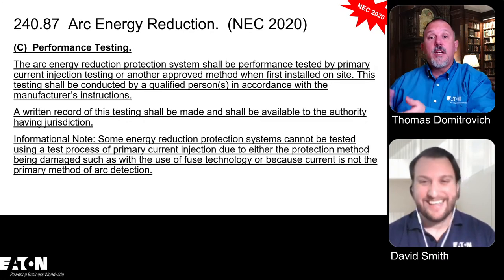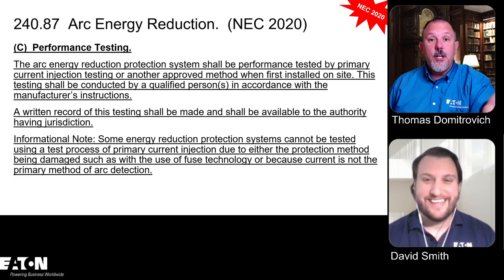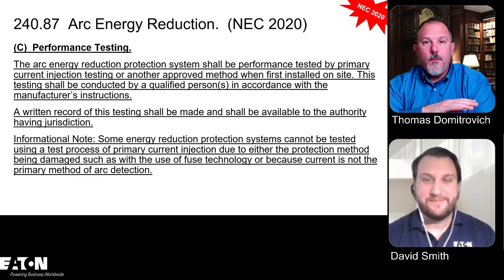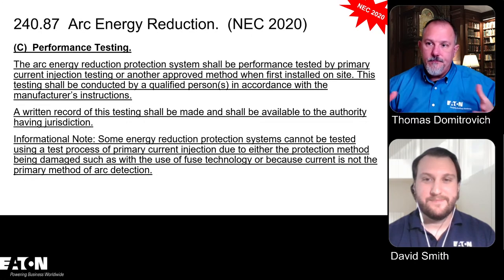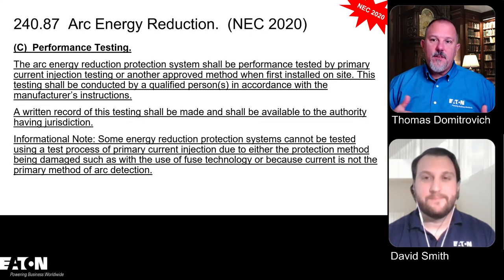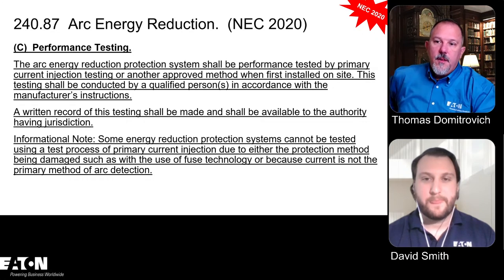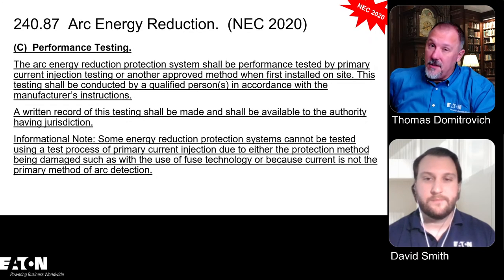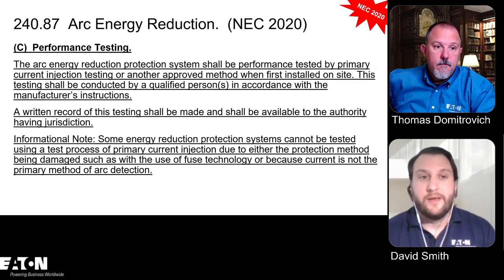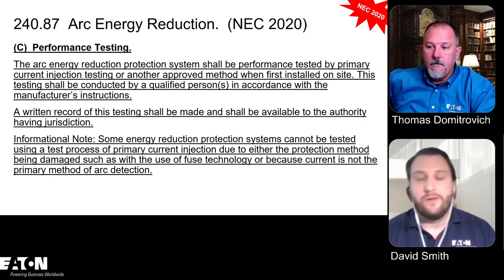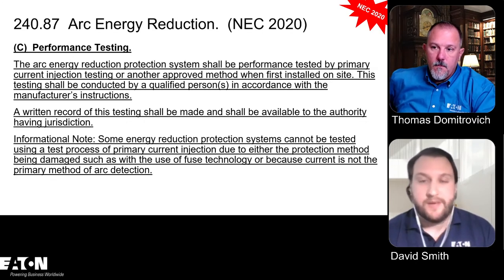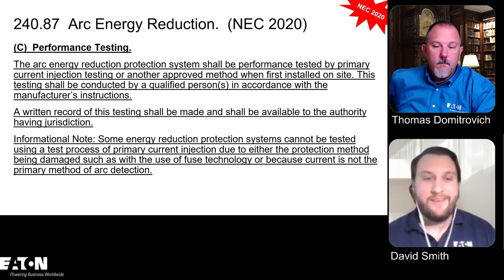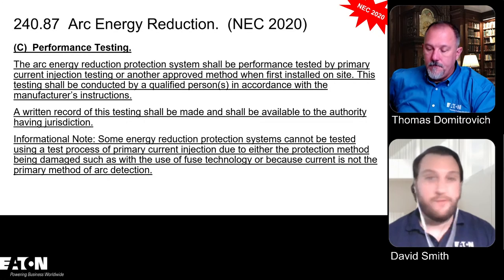And if you take technologies like the arc quencher, it needs current and it needs light sources. The arc energy reduction technologies that you use may vary. We had to point people to the manufacturer's instructions and other methods because that might be what you need. They may tell you, you put current through this and you're going to buy another one. Sure. And it's future-proof, right? The idea is to allow that leeway for future better technological advances for better testing. And that's why we have item C on 240.87, right? That's why we have or other approved means.